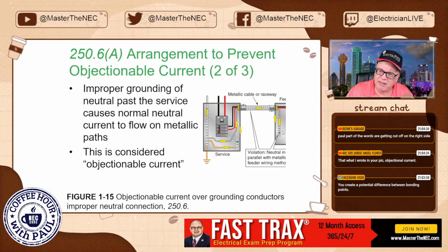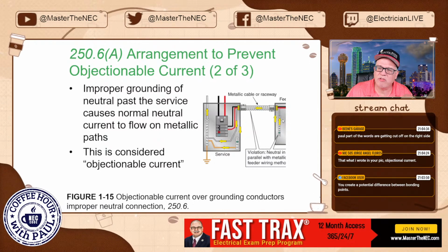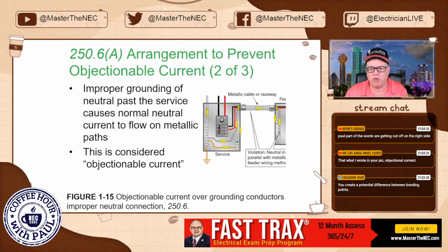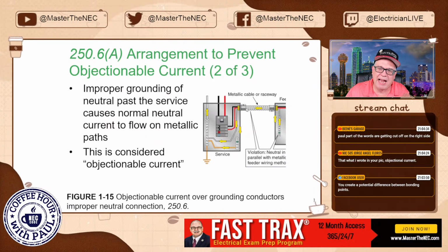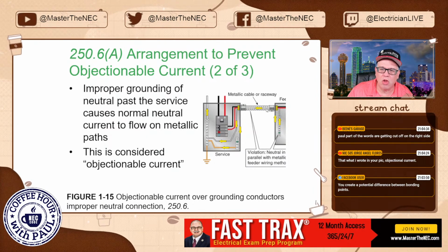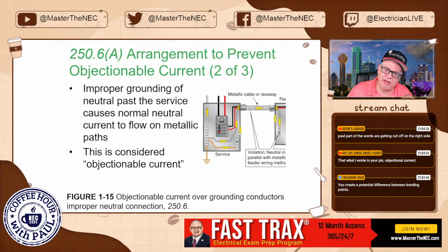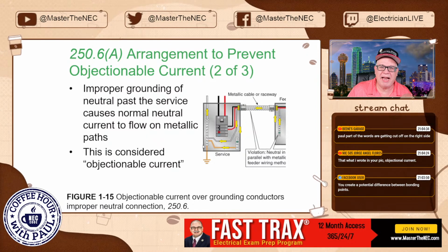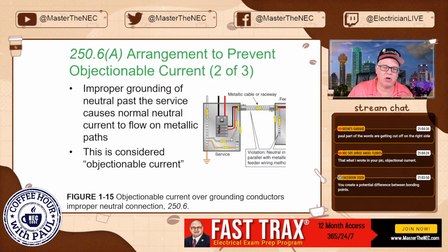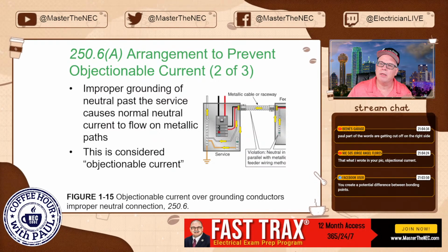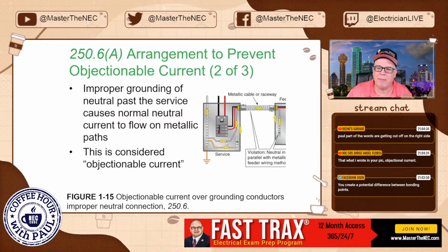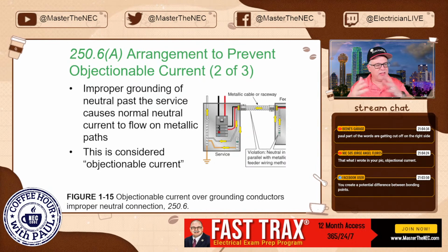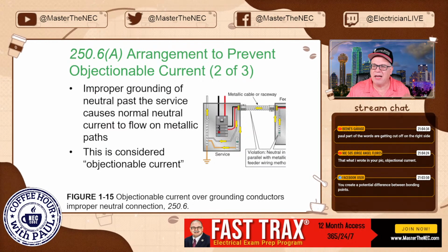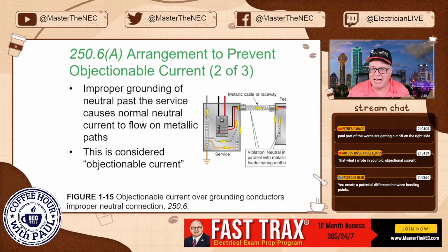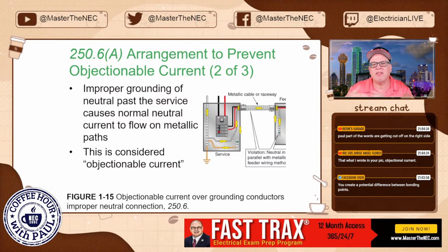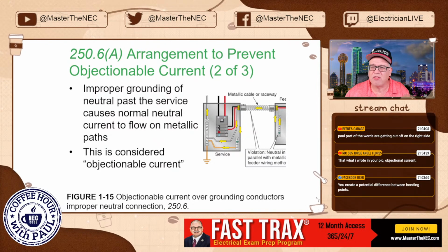So we assume this has all been installed properly. But by them putting in this screw right here, now what you've got is normal current that would be traveling on a neutral is going to also be coming back on other paths, okay? All the way back. And what this does is create, as you notice here, parallel paths. And it also creates objectionable current traveling on unintended paths. And so in that case, you also have to worry about things like how these circuits are run at this point and how they start to separate. And you could get some induced voltage from that. Probably not a lot. But again, these are things that you gotta not do. This is a prime example.